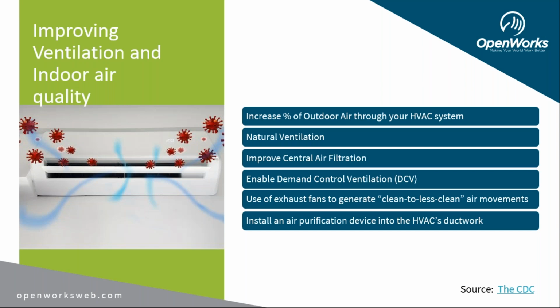Our next strategy is called demand controlled ventilation. This is basically a cross between energy saving strategies while also meeting fresh air initiatives. And you do this by actively monitoring the indoor air quality of the space. You would have to have an economizer tied to a CO2 sensor that is in the occupied space. The CO2 sensor monitors the building's ability to ventilate occupied spaces to be sure the air is staying clean. It then allows us to adjust how much fresh air is coming into the HVAC system through the economizer, while also looking at the outside air temperature and humidity to decide if it makes sense to run the mechanical cooling compressor, or does it make more sense to just bring in fresh air and we can cool the building off in that way.